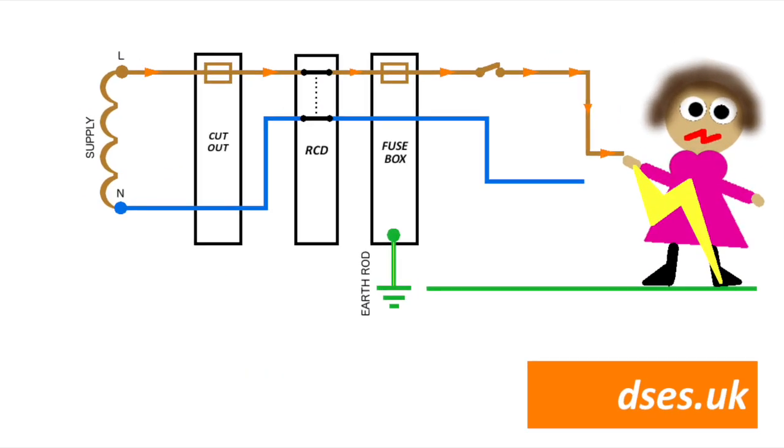And this is why the residual current device is a better option in modern installations. Unlike the voltage operated earth leakage circuit breaker which requires a connection to earth and for a fault current to pass through it in order to operate, an RCD has no connection to earth at all. An RCD effectively monitors the current going out against the current coming back and will trip off if there is an imbalance between the two. It isn't concerned about where that current is leaking.